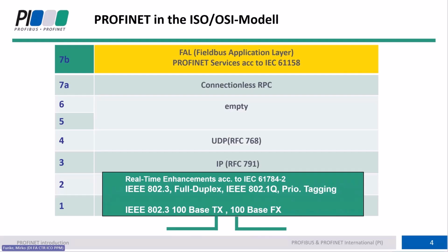Let's imagine we have an analog input module, and that module can be switched between current and voltage measurement, so you need to parameterize this. Or you can maybe change the measurement range between 0 and 10 volts or 5 to 10 volts, or whatever. This change is done in the configuration phase, and it is described how this is done. This is the fieldbus application layer.